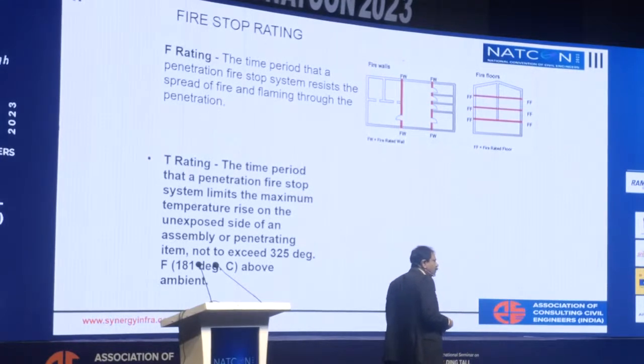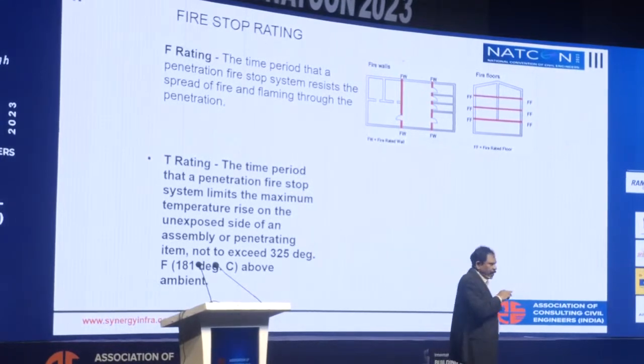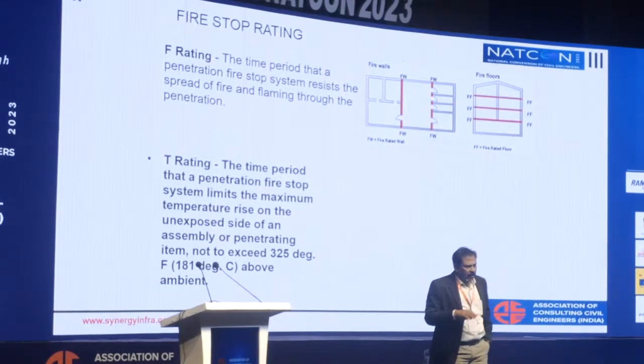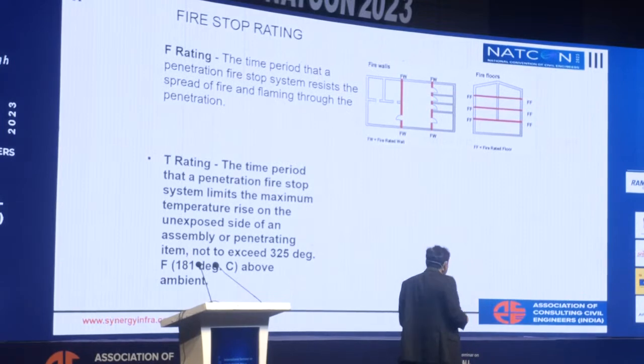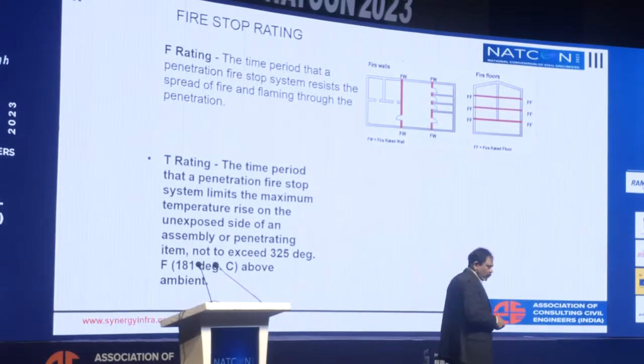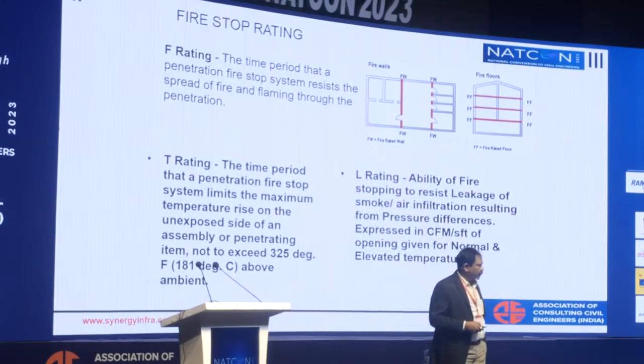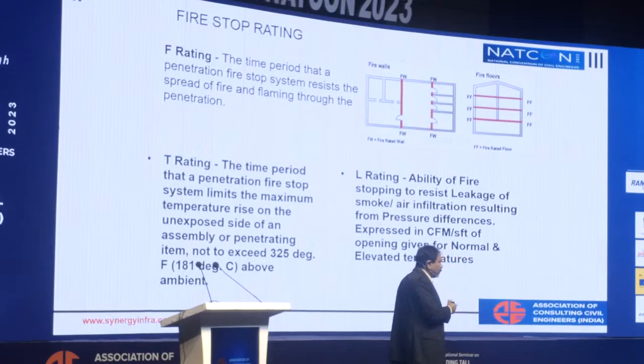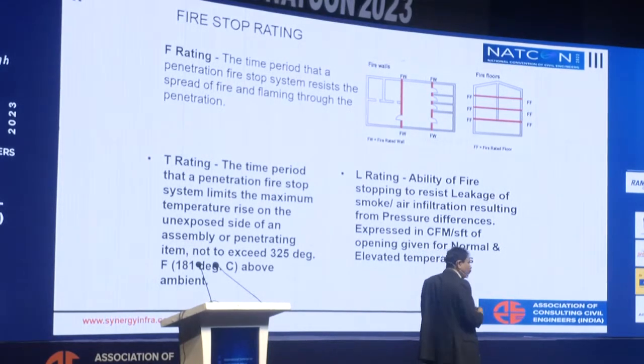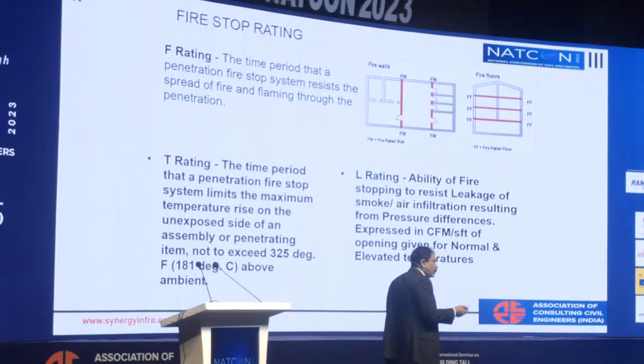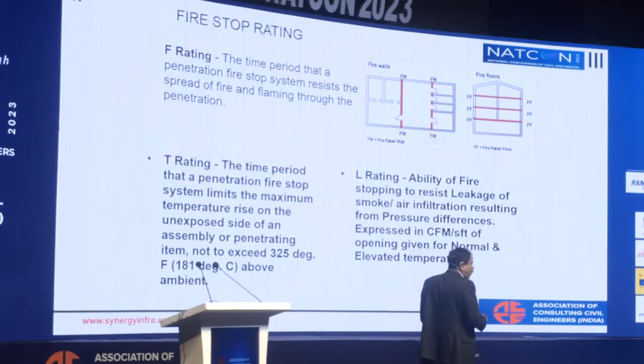The fire stop is mostly important when we are making a separation between the vertical floors. Then we need to have fire stops, and the fire stops have to be decided based on engineering judgments. And they need to have definitely 3 types of rating systems. One is F rating and T rating. The F rating is the time period that a penetration fire stop resists the spread of fire. Similar to any kind of fire door, whatever the temperature, the time, 60 minutes or 120 minutes, it should be able to withstand that kind of fire.